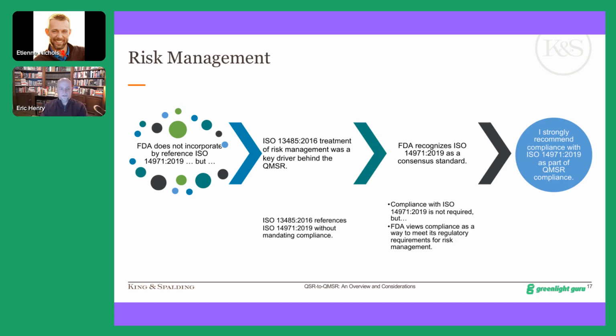Because of those reasons, I strongly recommend that even though it's not required or incorporated by reference in the QMSR, while you're remediating your quality system—bringing in ISO 13485:2016, bringing in clause 3 of ISO 9000:2015—bring this in as well. If you're not already complying with it, do so. Not because the FDA told you to, but because it's the right thing to do.